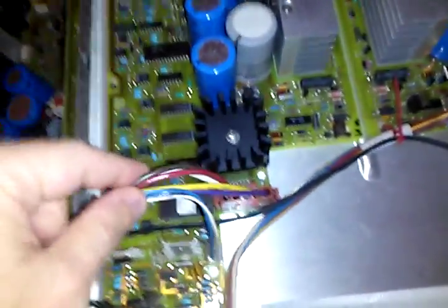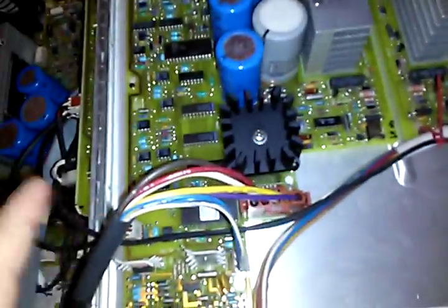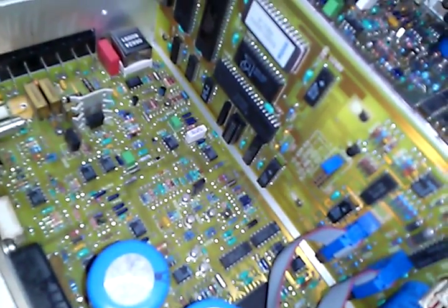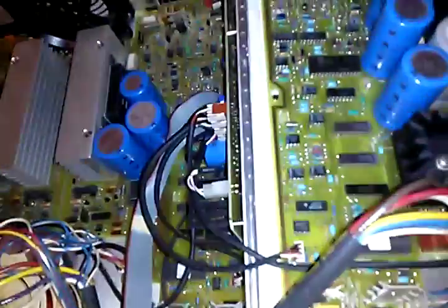Everybody, I'm back, and what I've done is I rehooked up this board, which was disconnected the last time, and I changed this jumper back to normal operation. Basically, where the jumper was before, it bypassed the self-test, and of course I didn't want this connected if it's failing and it bypasses the self-test. With it in the condition that it is now, it'll run diagnostic tests on everything. And if it finds a fault, it basically disables the entire system so that there's no potential problems.